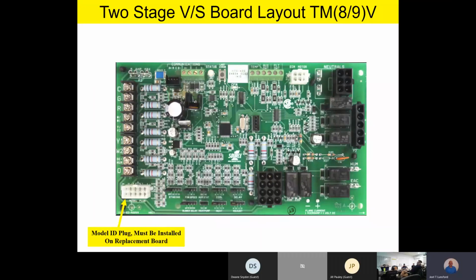The final component on this board I want to talk a little bit about is what we call our Model ID plug. It's just a plug that has some simple wires on it. It isn't like a personality module or a jump drive or a USB or anything complicated. It's just a simple wired plug that tells the control board what size furnace it's hooked up to. So now instead of having 47 different boards on your truck, you have one replacement board, and that Model ID plug tells the board what size the furnace is.